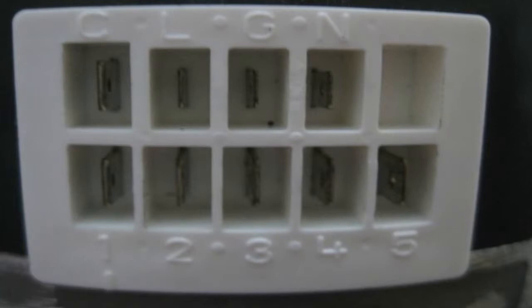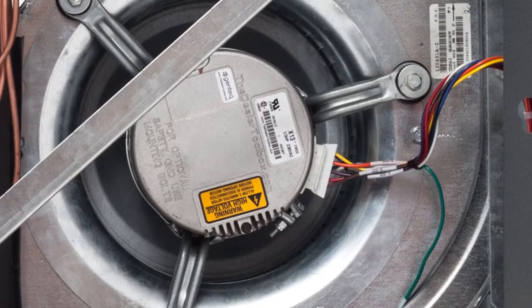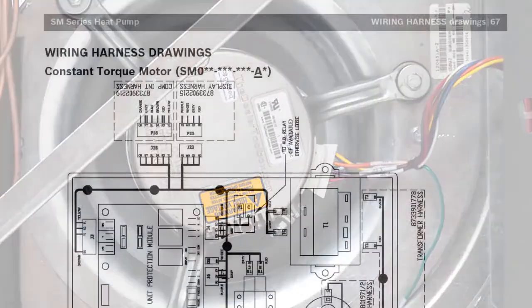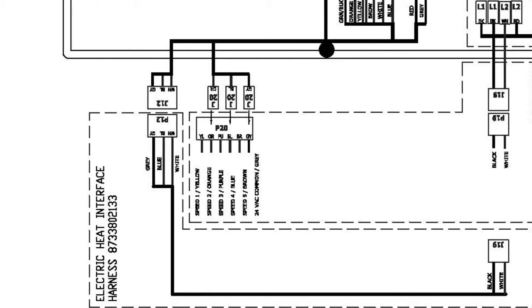A 24 volt AC input applied to one of the programmed speed taps at a time will run the motor at a constant torque. The motor speed is adjusted by simply manually moving the wires to the speed taps from one tap to another. One of the new features of the SM model is that the motor speed taps can be changed in the electrical box or the E-box via a 6-pin connector labeled P20. You can see that illustrated in figure 120 on page 67 of the installation and maintenance manual.